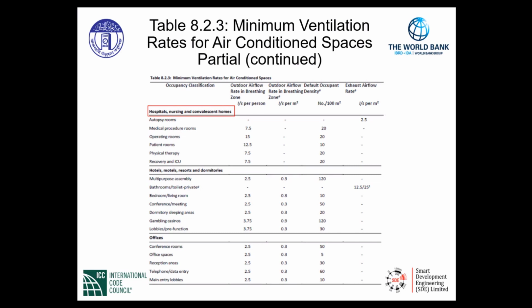Another part of the table, continuation, indicates the occupancy classifications. Hospitals, operating rooms. We can see here the operating rooms have a very, very high outdoor airflow rate in the breathing zone at 15 liters per second per person. And again, we remember where that requirement comes from, and we see the high airflow rate in these operating theaters. Patient rooms give us 12.5 liters per second per person. And as you can see, based upon the function of the area, physical therapy, recovery, and ICU, both have 7.5 liters per second per person as a minimum requirement to provide that outdoor airflow rate in the breathing zone per person.